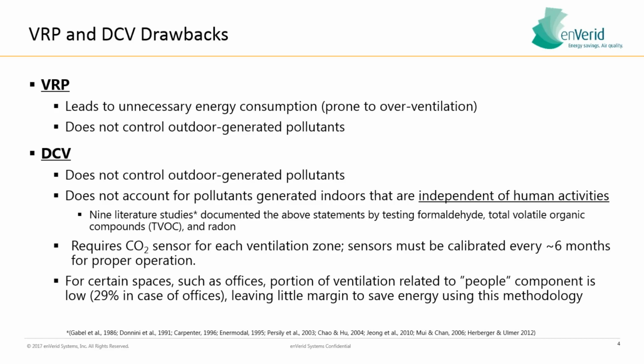So ventilation rate procedure might not be dilution within buildings, especially in polluted areas, maybe Colorado, where you've got higher ozone levels outside. You can't ventilate out ozone. So ventilation rate procedure might not be the best path to go. And there are some changes in 2019 ASHRAE that actually specifically call that out. So stay tuned. Demand control ventilation also doesn't control for outdoor generated pollutants.